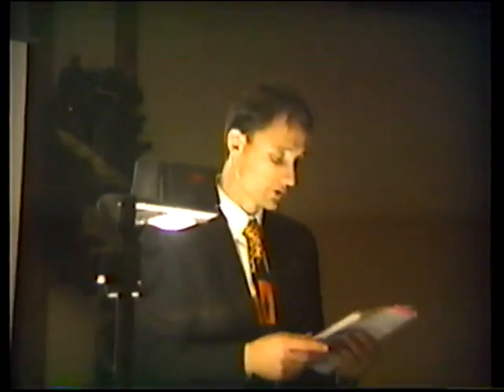So in order to be able to say, well, how the heck am I going to design a system to meet that? You still have a choice to go back to your standard prescriptive design, but if you wanted to do a performance-based approach, here's some guidelines. They say you have to demonstrate that you meet that criteria. And the only way you're going to be able to do that is follow some engineering methodology. That's why the codes are trying not only to put some of this performance-based language together, but we have to have reliable engineering data and calculation methods that are defendable. They'll go back in after and put in a lot of the same design criteria that you will look at.